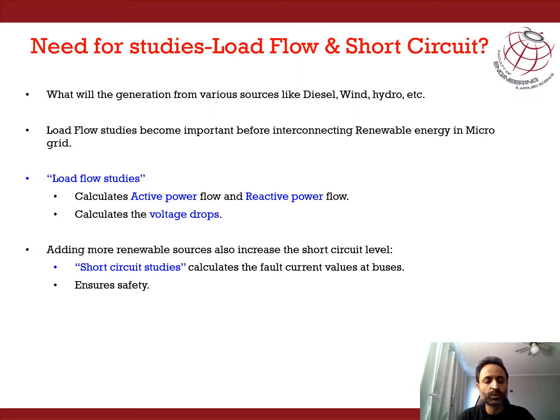Now, when we add more and more sources like hydropower and wind turbines to the microgrid, this will also increase the short circuit ratings at the various buses. So there is a need to carry out short circuit studies also. These short circuit studies will give us the various fault levels at the various buses in the microgrid. To ensure safety, we need to see that these fault levels, which are obtained through the calculations, are less than the ratings of the equipment available in the industry.